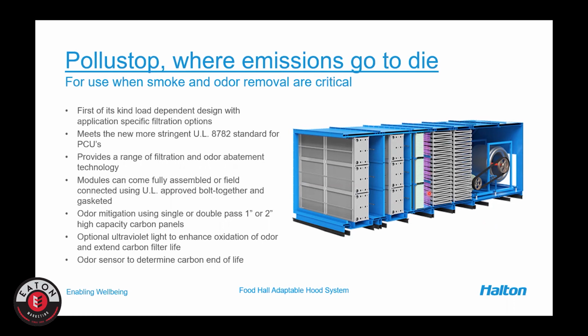Here is a section of UV light with 2 carbon sections here. This is a double pass electrostatic section here. So we're collecting the grease in the first module, addressing the odor in the second module, and then the exhaust module will be the last. And this is a modular unit. These can be split up if needed. Once the CFM, the exhaust requirements of the system, are set, the width and the height of the unit don't change, but as we add features, the length of the unit can certainly tend to grow.